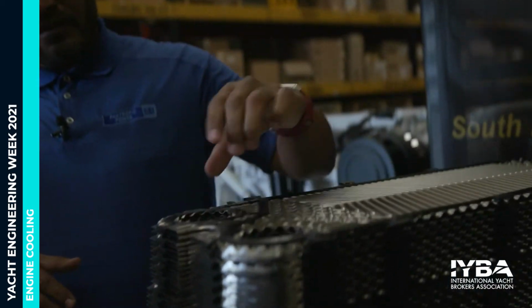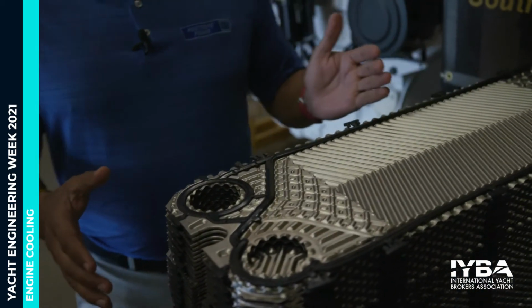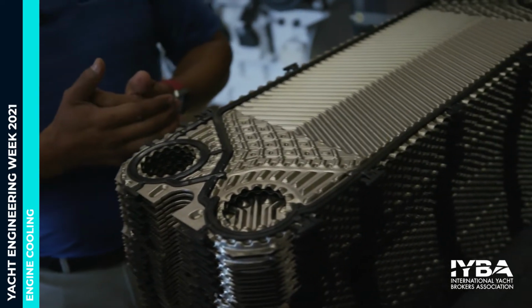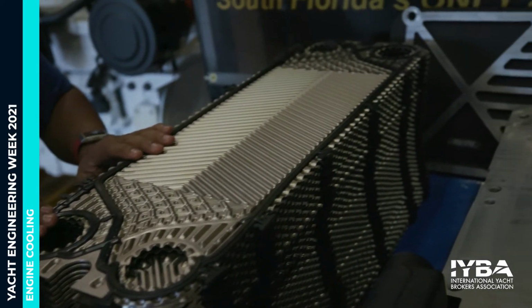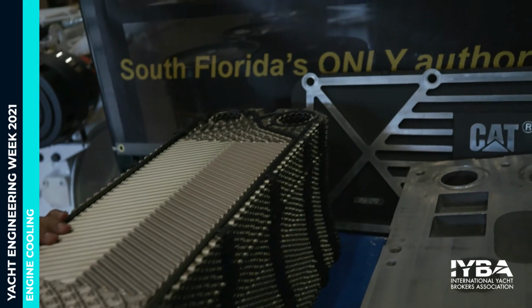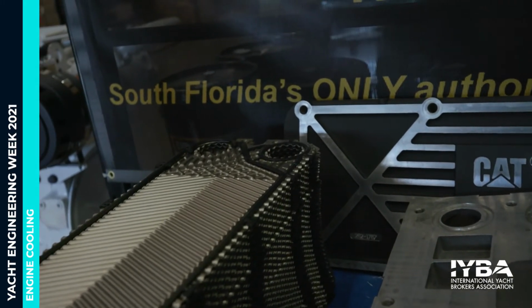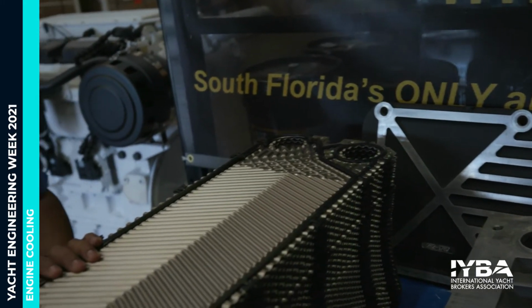Gaskets are very important. If you maintain your heat exchangers properly and stay on schedule, you can get 3,000 to 4,000 hours out of these gaskets, which is a long time — more than the useful life for most owners.